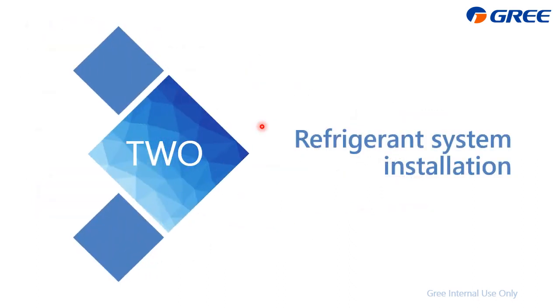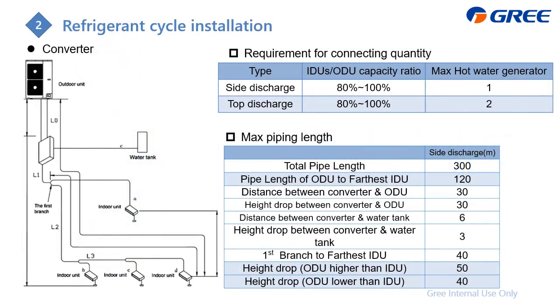In the second part, we will focus on how to install the refrigerant system. For the refrigerant cycle, first are the requirements. For both the side discharge and top discharge, the indoor units divided by outdoor units capacity ratio is only from 80% to 100%. As for the upper limit of the hot water generator, for side discharge, only one. Top discharge, it can install a max of 2.